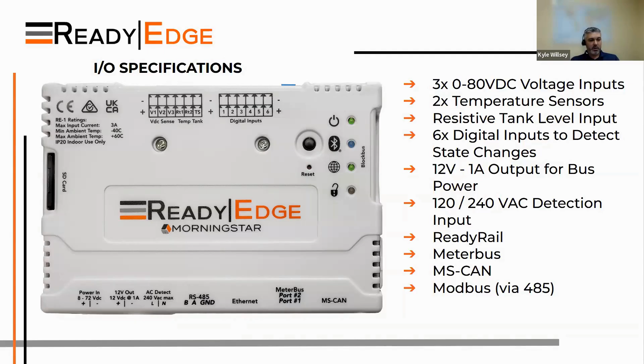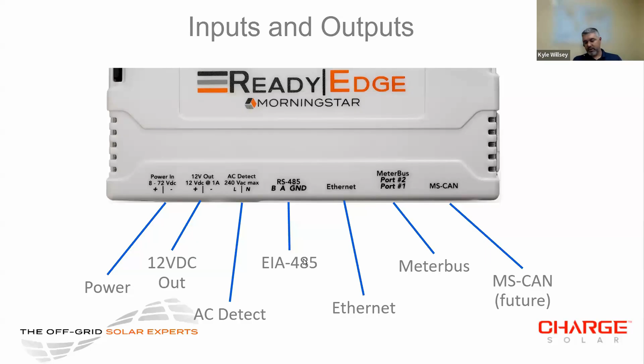So here's a deeper look at the bottom. We have the power input on the left, the 12 volt DC out - it's only rated for 1 amp. It's not intended to be a power supply, but it's a nice, simple 1 amp output signal to give you either power to that 485 bus, which typically needs 12 volt power, or it can be used in a generator starting application in some cases.